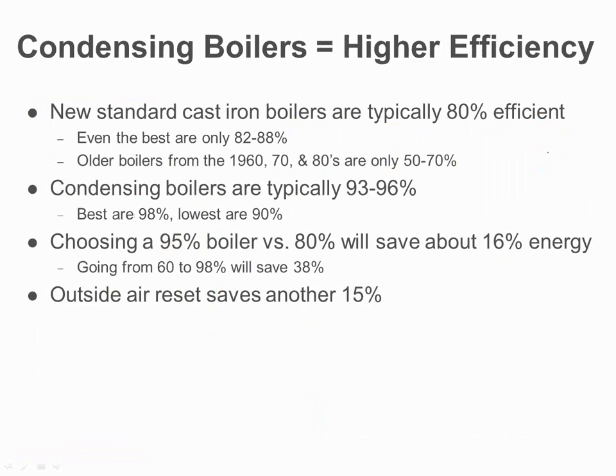The efficiency of condensing boilers is the main driver on why we want to put them in. Yes, we have to change your boiler out because your boiler's dead, but we'd also like to save you some energy in the process over the next 15, 20, 30, 35 years. Most of the boilers we take out of a building are probably about 80% efficient when they were brand new. A lot of times they'll be less than that. The dirtier the heat exchangers get, the less efficient they are. Additionally, older boilers weren't even 80%. If you're taking out boilers from the 70s and 80s, they may be 55, 60, 65% efficient. So you want to find out how efficient the old boiler is that you're taking out, and how efficient the new boiler is that you're putting in. With that information, you can quickly calculate for people how much money they're going to save, which is obviously the first question they're going to ask you when you mention a condensing boiler.